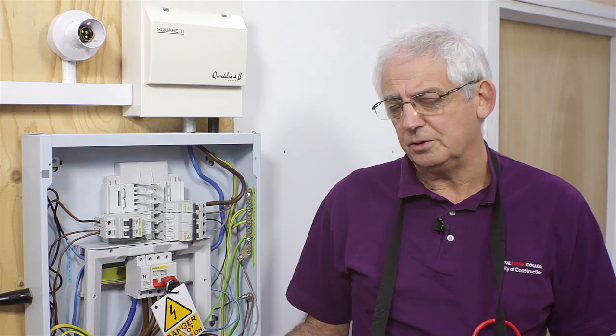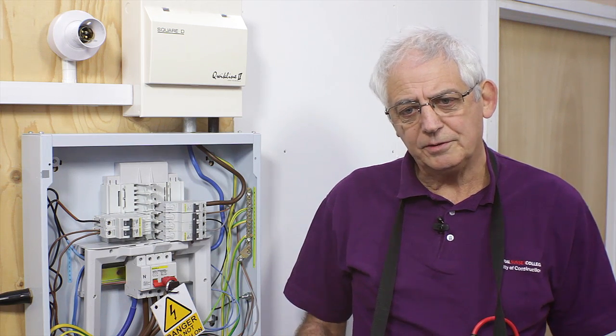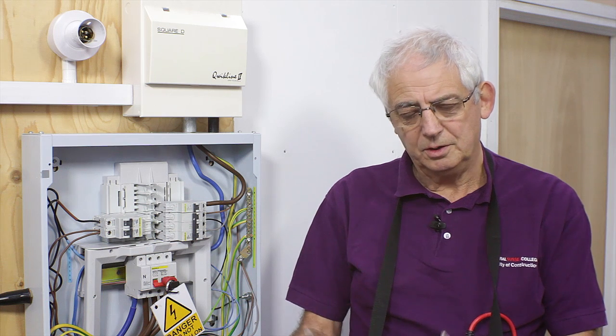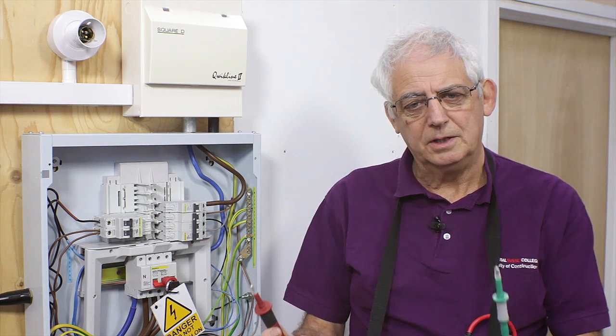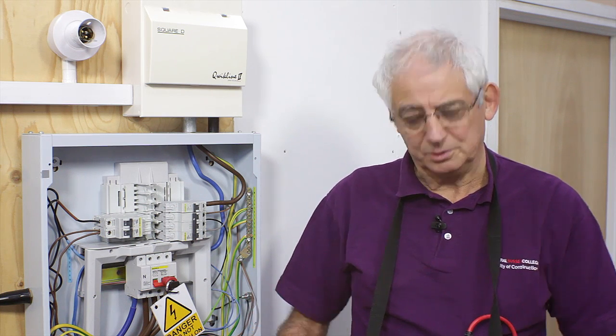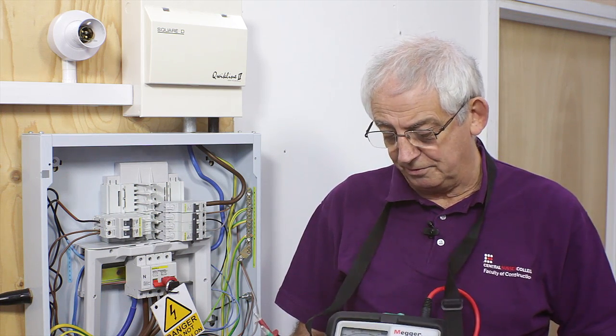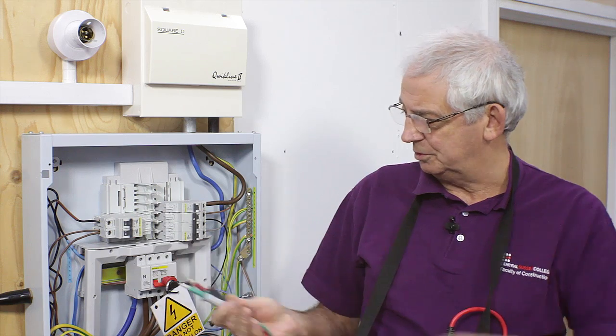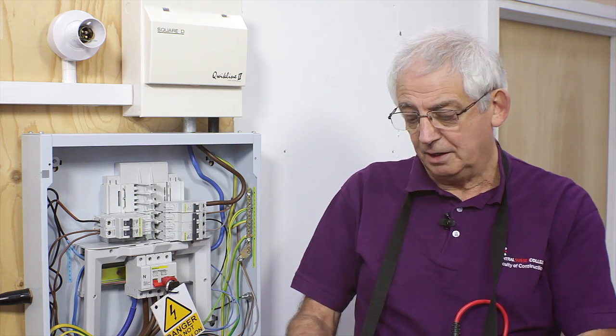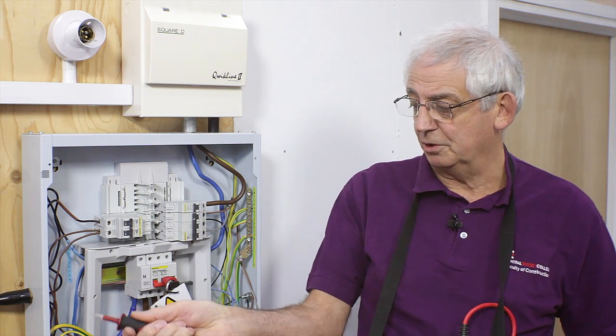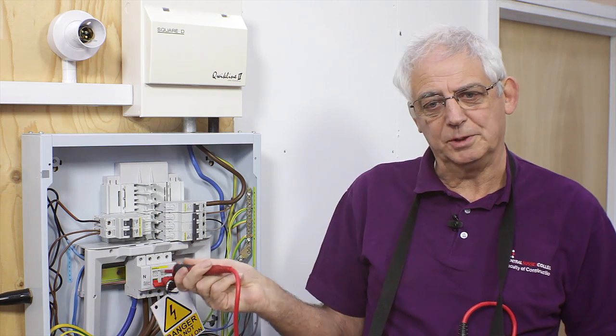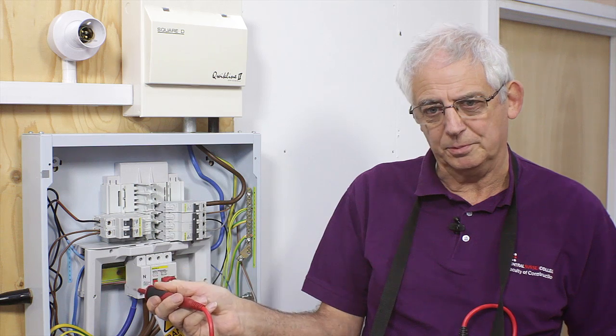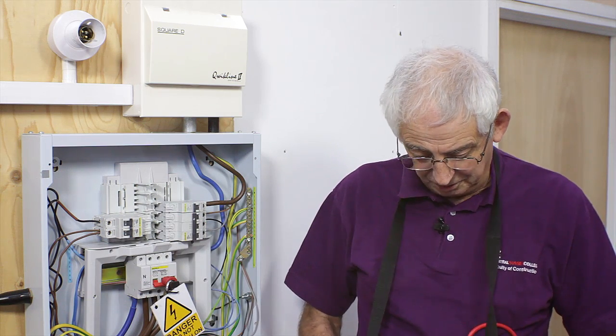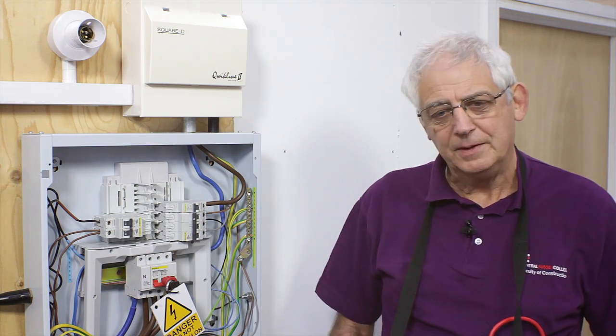Because it's a 500 volt test, you have to push the button to liven up the probes. And for that reason, of course, you do need to push the button. If you're not careful, it can be very difficult trying to hold probes on and push the button at the same time. I've got a special probe here, which has got a button on the end of it, which allows me to operate the device from the probe, which is obviously a good idea, makes life a lot easier.